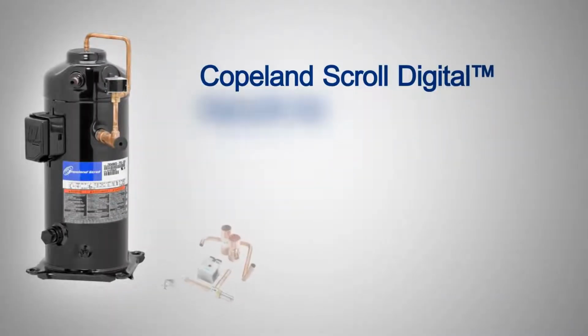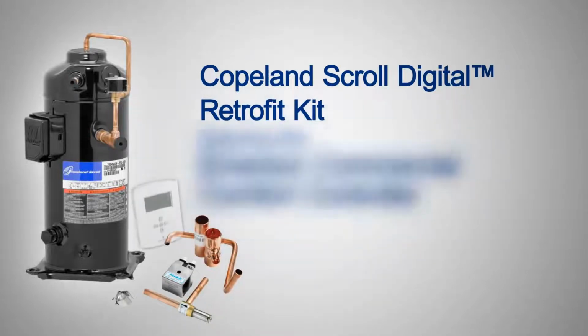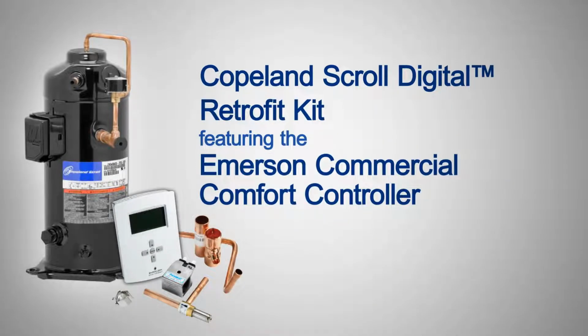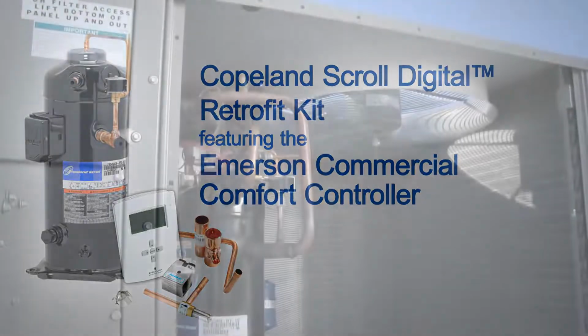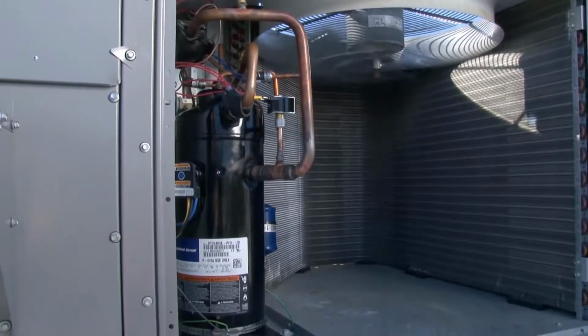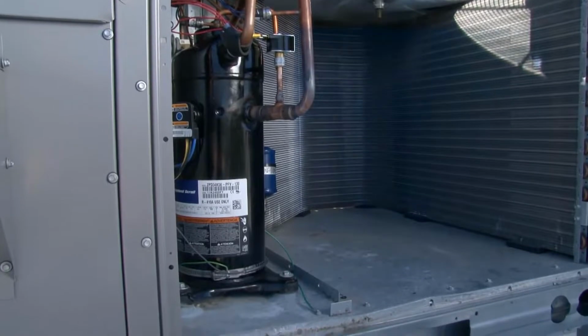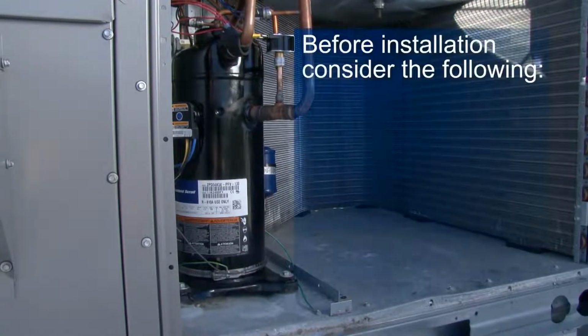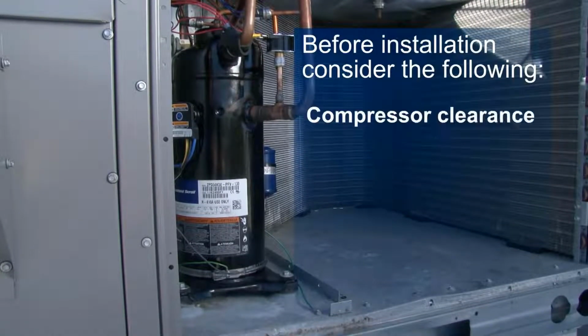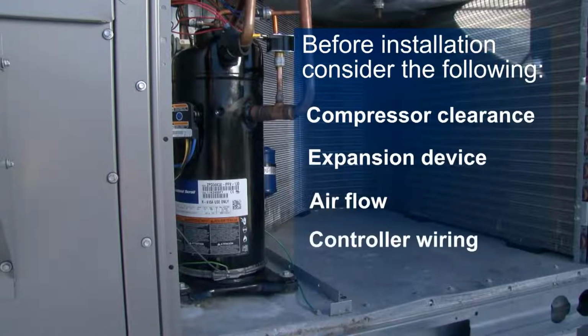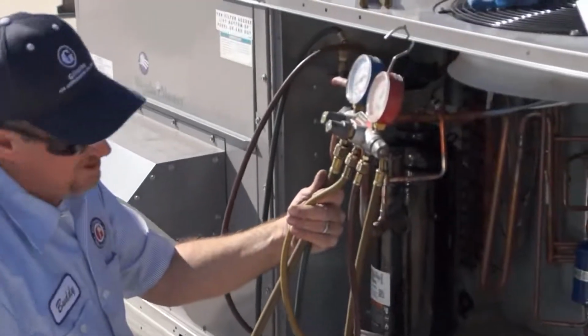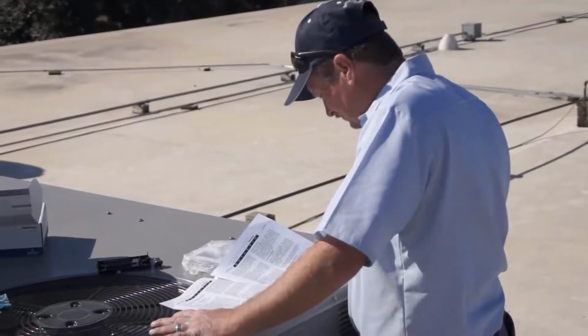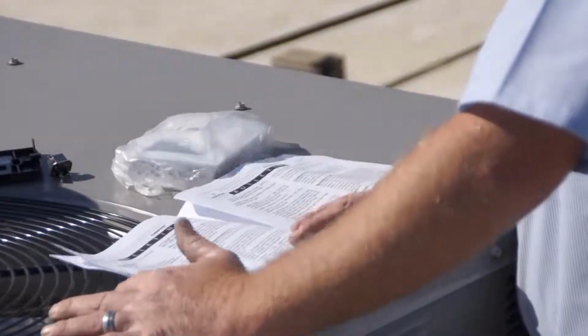The following video outlines the steps necessary to install a Copeland Scroll digital compressor using the Copeland Scroll digital retrofit kit featuring the Emerson commercial comfort controller. Before beginning any new installation or retrofit of an existing compressor, be sure to consider all system and component implications such as compressor clearance, expansion device, airflow, and controller wiring. Ensure that all proper safety equipment is used and procedures are followed, and that all relevant product manuals have been read and understood.